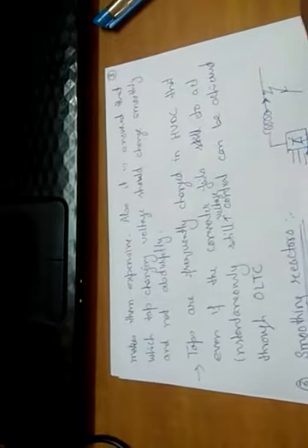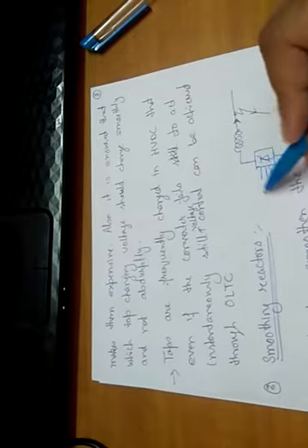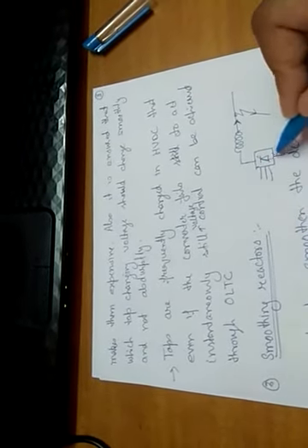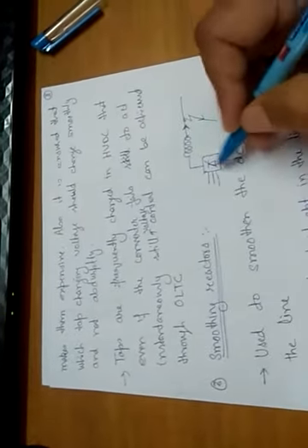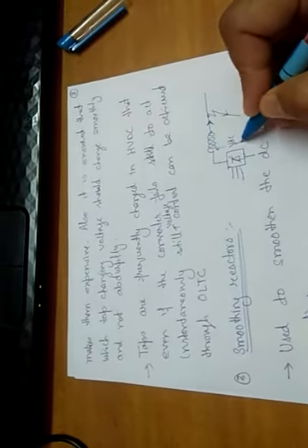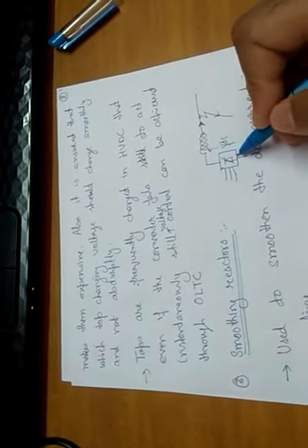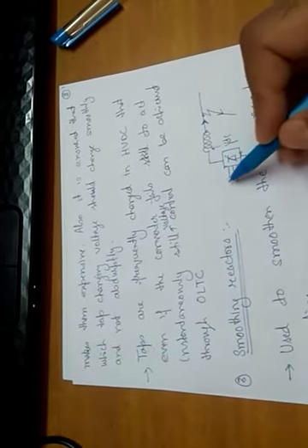Now one more point here, that these taps are frequently changed in HVDC system. Though we can control the voltage by changing the pulses here, this OLTC is so frequently used in HVDC system that even if this system fails or exhausts, meaning it is not responding immediately to changes, and we want this VDC to remain constant, we can achieve this by changing the OLTC as well. Even if this converter or valve exhausts, still control can be achieved by changing the taps of the OLTC.